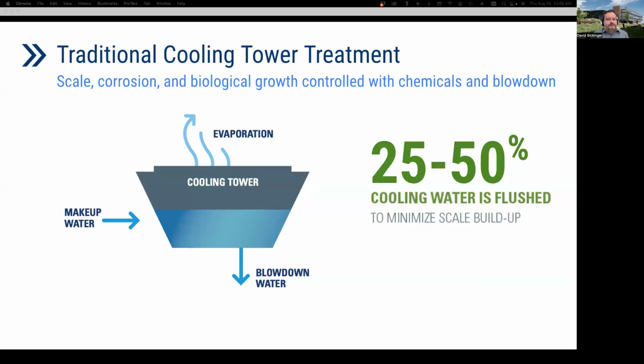Next slide, please. Just a brief background on cooling towers. They are an integral component of many refrigeration systems, providing comfort or process cooling across a range of applications. Open loop cooling towers reject waste heat to the atmosphere through evaporation. The operation consists of cascading water across the medium, with resulting evaporation cooling the water, thus allowing heat to be effectively transferred to the atmosphere. However, as part of this process, minerals become concentrated in the water that remains, which can lead to accelerated scale or mineral deposits, corrosion problems, and biological growth.